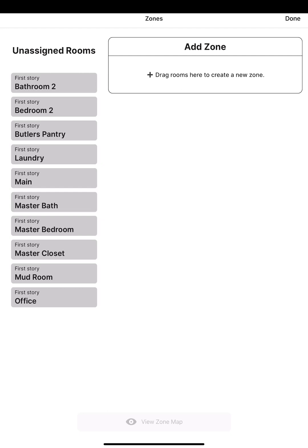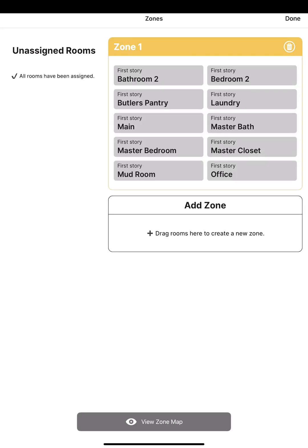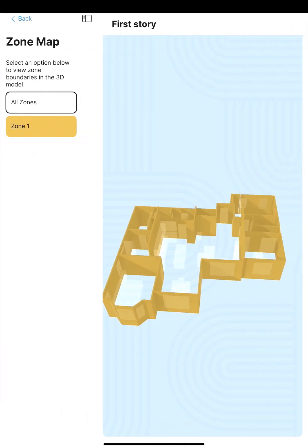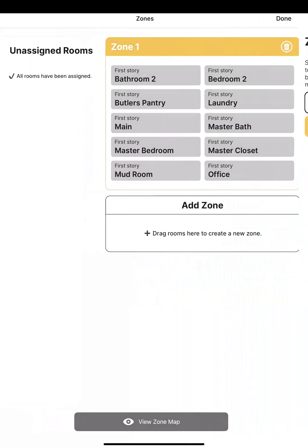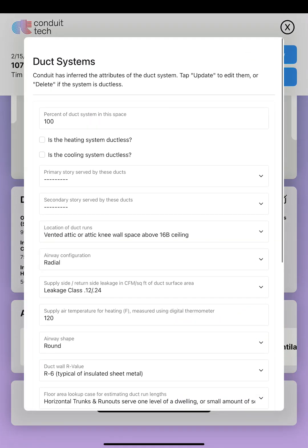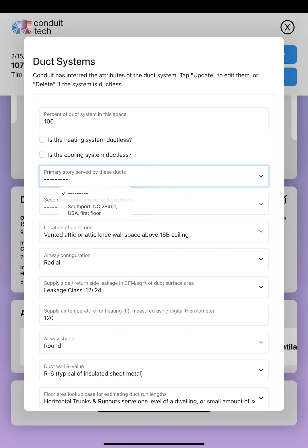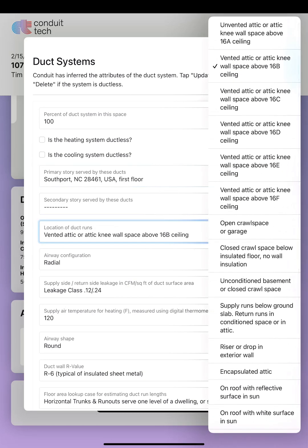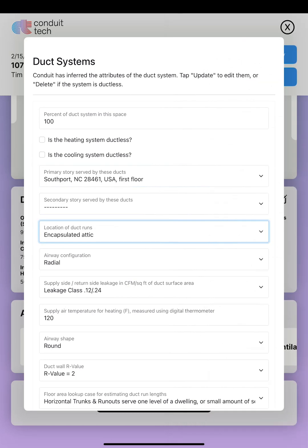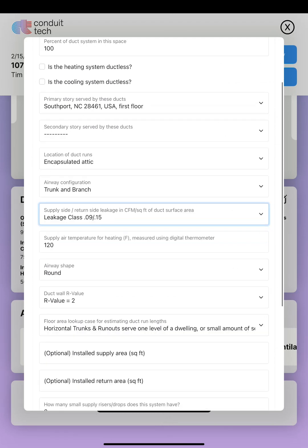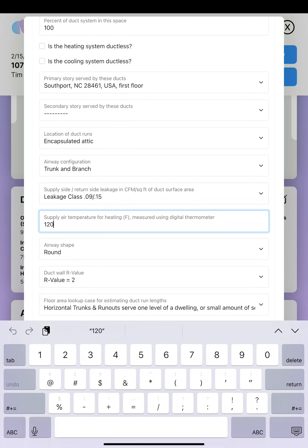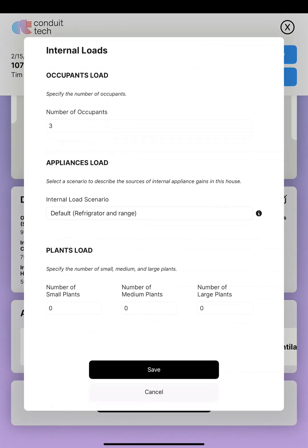If you're zoning your house, you have the ability to do that here. I don't have any zoning, so everything goes into the same zone. If you want to view your zone map, it'll show you how your house is broken up. For ductwork, mine is in a conditioned space — it's in an encapsulated attic, not a vented attic. It even differentiates between conditioned space and encapsulated attic. For supply temperature, a gas furnace will have a slightly higher supply temp than a heat pump — I'm going to put 100 degrees for heat pump.